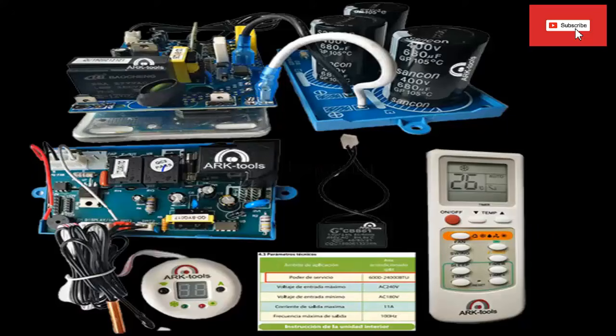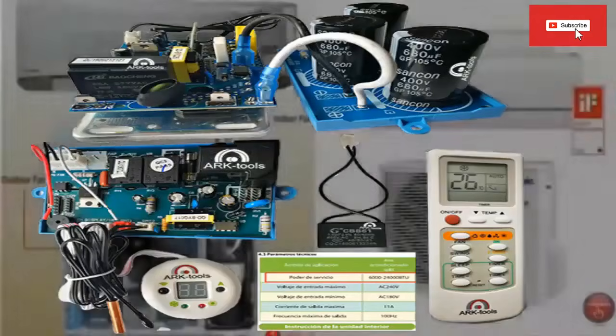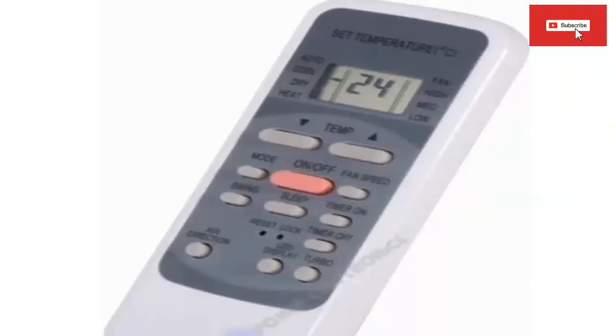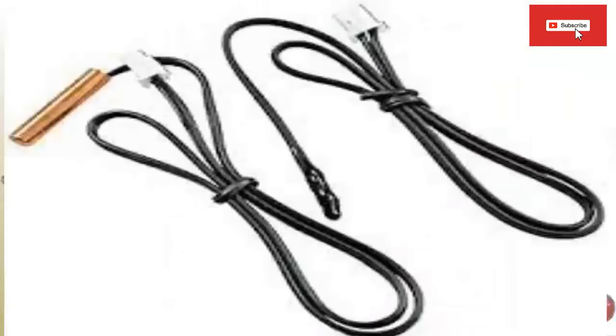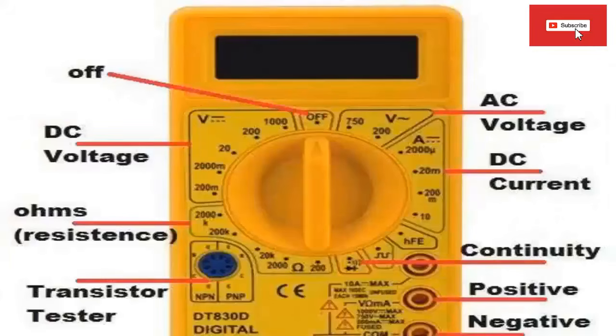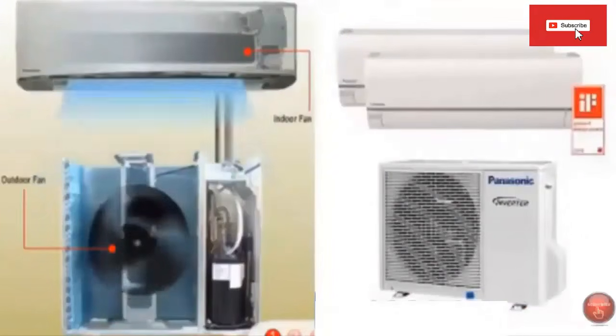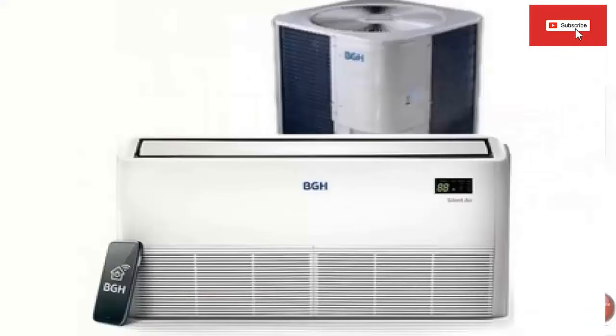In some equipment, when the air conditioner shows code 1 on the display panel and does not turn on, it means that the thermistor in the room is shorted or faulty. Disconnect the ambient sensor and check its electrical resistance with a multimeter, using the kilohm scale. The thermistor must show an electrical resistance value according to its characteristics, and never infinite or zero resistance. In air conditioners with 3-phase power, when the phases of the power supply are not connected in the correct sequence, the equipment may display the error code 1.